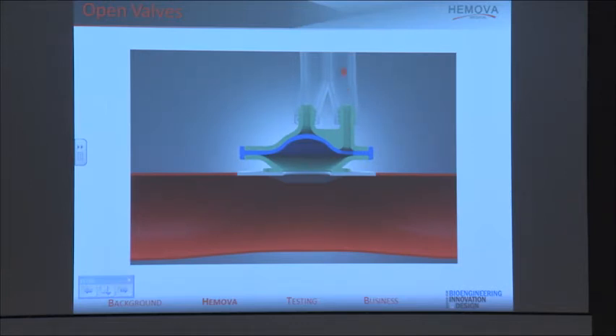After the dialysis session, the valve can be closed by pushing saline back into that center port and thereby flipping the valve down like this, enabling a flushing of the system without any interference with the patient's bloodstream. And you can see how the valve is designed to lay flush with the vein of the patient.